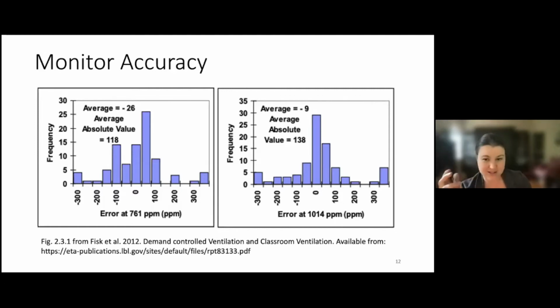Also, the age of the sensors didn't seem to make a difference. There were much older sensors that were working fine and newer sensors that were way off. They also found that although a lot of the sensors were calibrated at installation, it was a little bit hit and miss after that, so there were definitely some maintenance issues. In this particular study, the authors suggested that something like an electronic eye, a sensor or people counter to count the people going into the room, might actually be a better measure of occupancy than trying to use CO2, because these sensors were a little wonky.